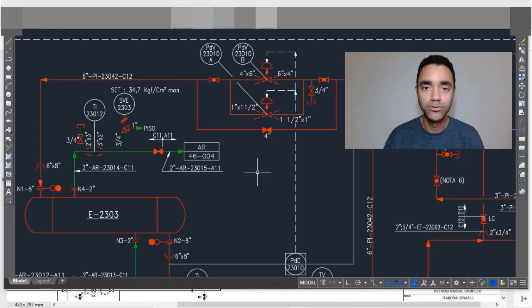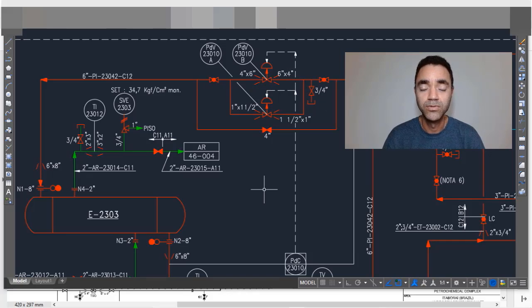See that this control loop is different from the previous arrangement, because now we have a split range control. Part of the signal will actuate the small control valve, and the remaining signal to the process will actuate the biggest control valve. Or it can be the opposite, depending on the control philosophy of the plant.